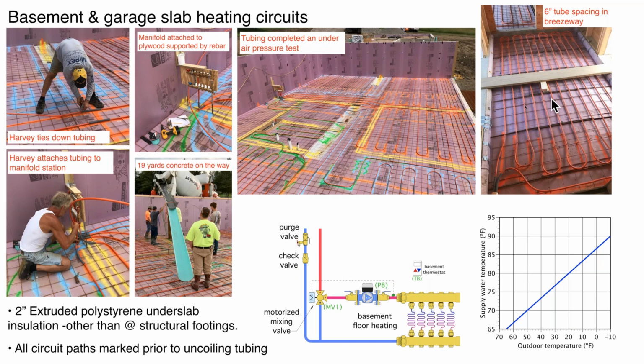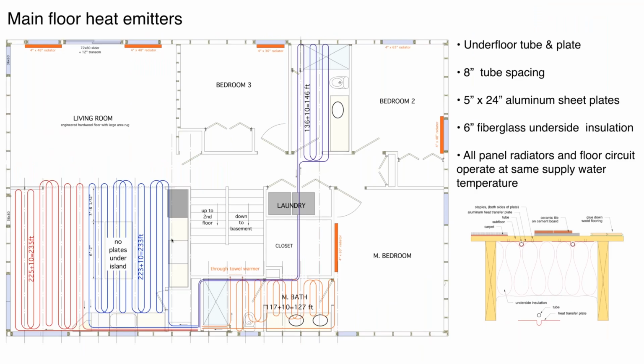Here's what 6-inch on center tubing looks like. That's the breezeway. You can see they've extended the bends out a little bit to take some of the stress off the piping. And when that's poured, that mesh and tubing is all going to be lifted up to about half the thickness. Okay. Won't spend a lot of time on this.